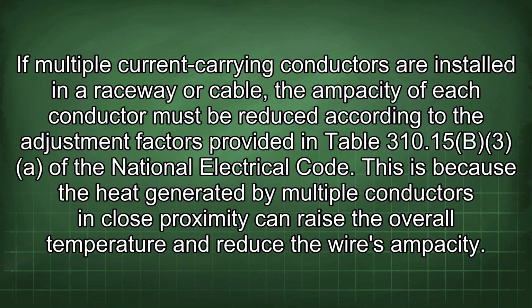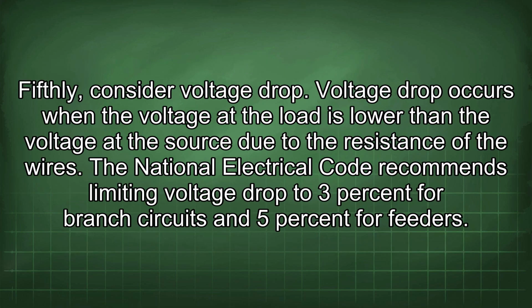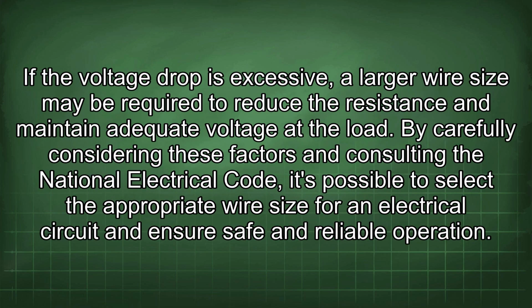Fifthly, consider voltage drop. Voltage drop occurs when the voltage at the load is lower than the voltage at the source due to the resistance of the wires. The National Electrical Code recommends limiting voltage drop to 3% for branch circuits and 5% for feeders. If the voltage drop is excessive, a larger wire size may be required to reduce the resistance and maintain adequate voltage at the load. By carefully considering these factors and consulting the National Electrical Code, it's possible to select the appropriate wire size for an electrical circuit and ensure safe and reliable operation.